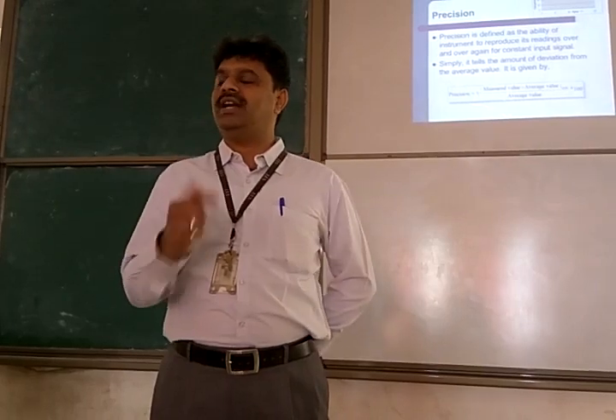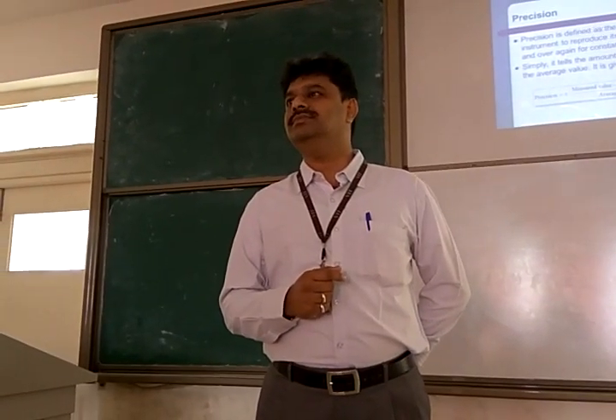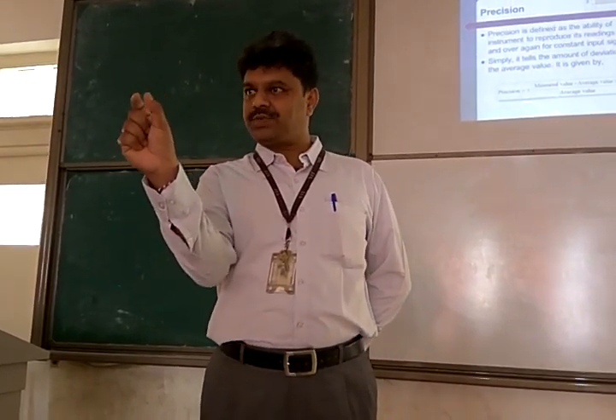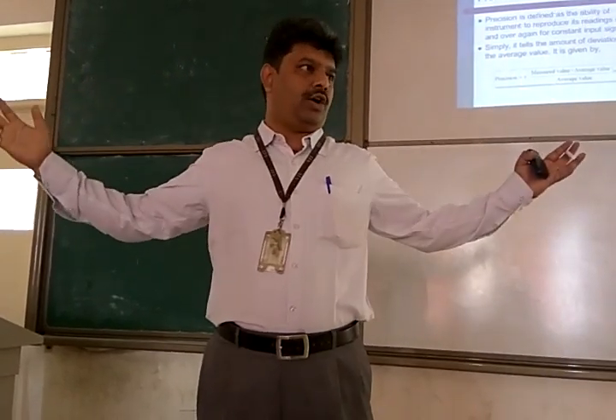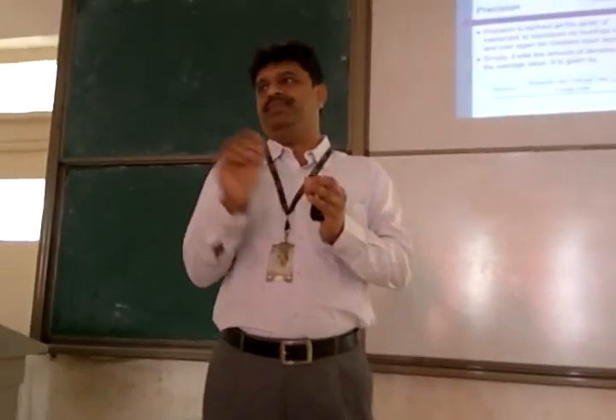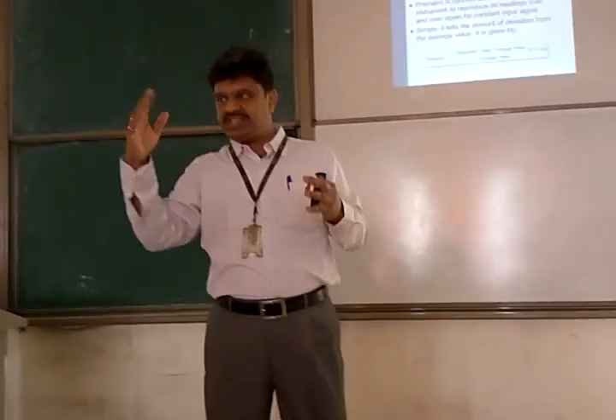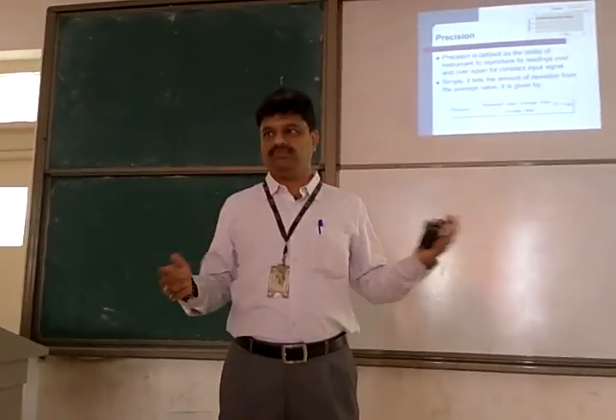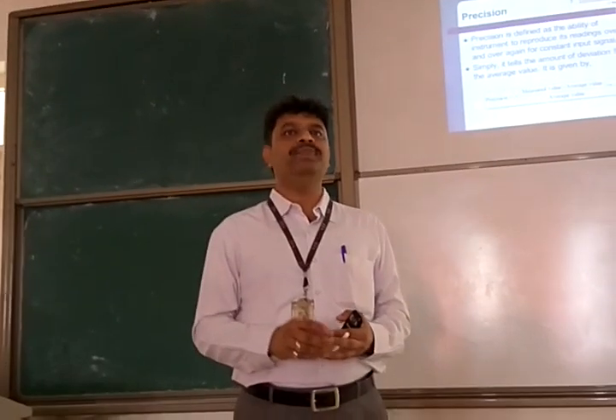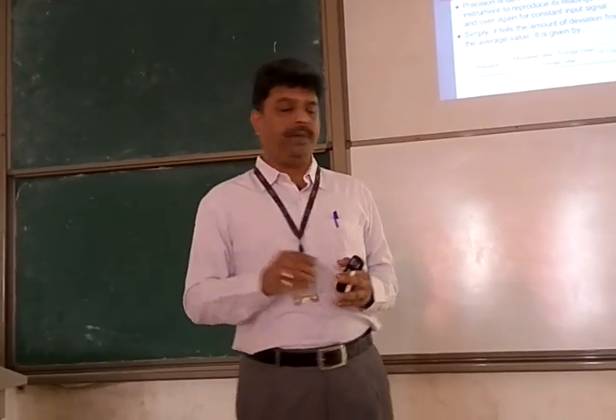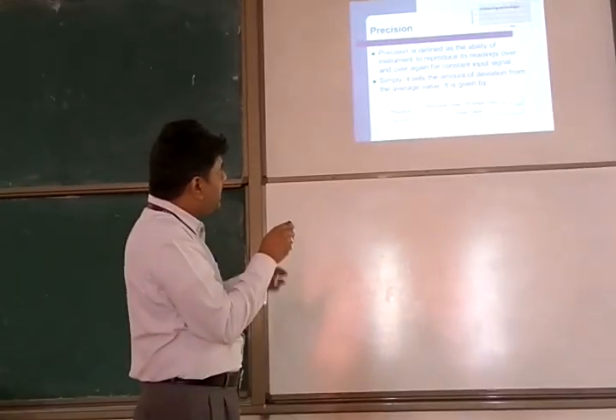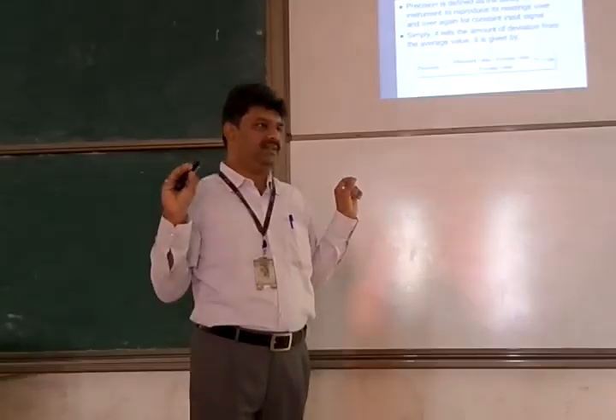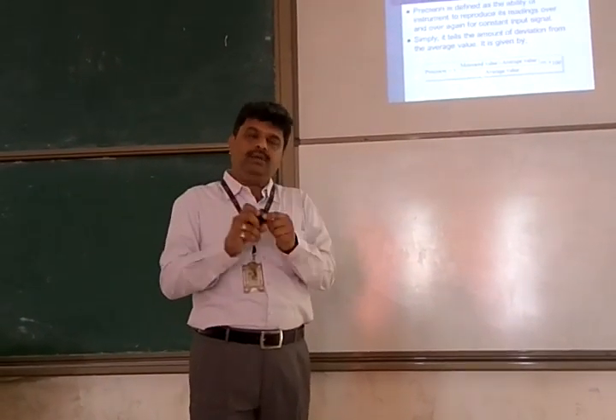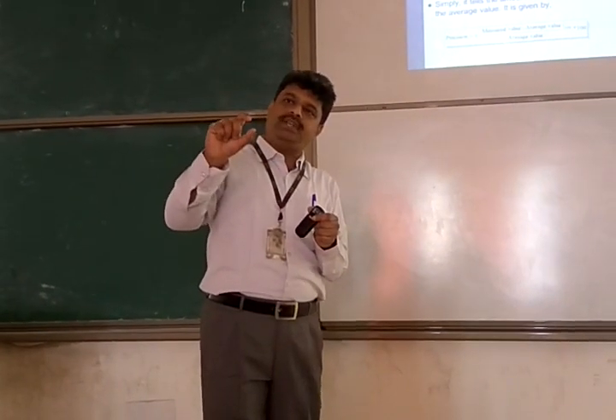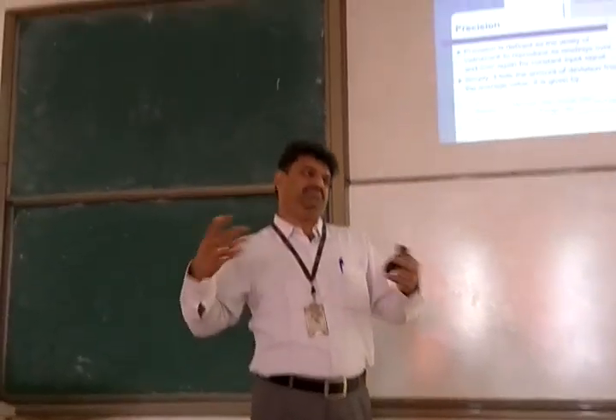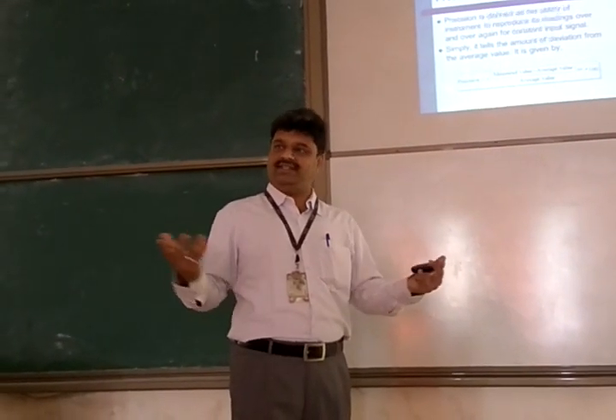Why is it related to standard deviation? If the standard deviation is small, that means the readings are not very spread out. They are lying closer to each other. If the standard deviation is high, that means the variation in the data is far apart, there are bigger differences. So it's something like standard deviation in statistics. The smaller the number, the more the instrument will produce its reading again and again close enough to each other. If the precision value is bigger, that means the readings will be scattered.